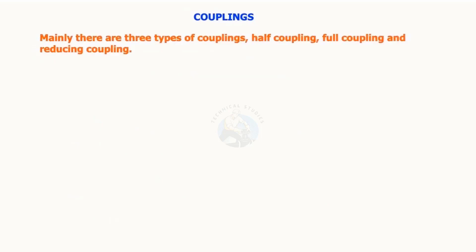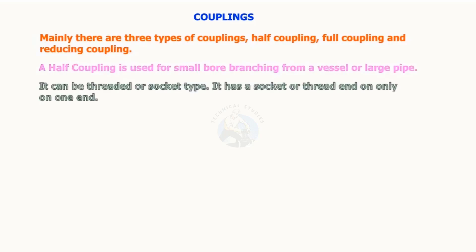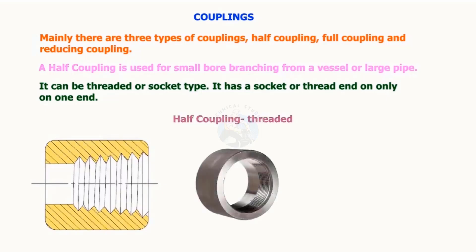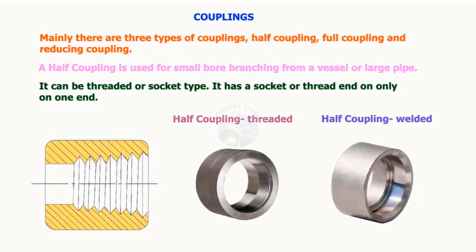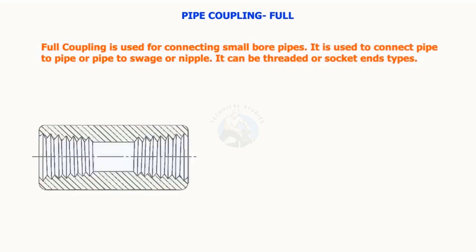Mainly there are three types of couplings: half coupling, full coupling, and reducing coupling. A half coupling is used for small bore branching from a vessel or a large pipe. It can be threaded or socket type, and has a socket or thread end only on one end. Full coupling is used for connecting small bore pipes. It is used to connect pipe to pipe, or pipe to swage or nipple, and can be threaded or socket end types.